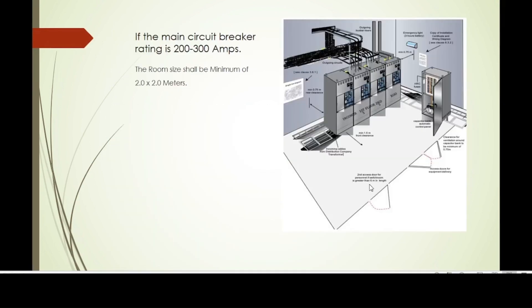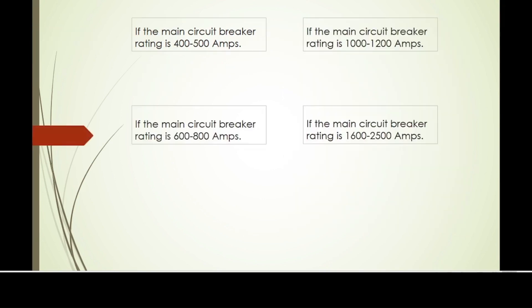As per ADDC electricity and wiring regulations 2020, appendix 8, there are certain minimum sizes for LV switch rooms based on their respective main circuit breaker amperes. For example, if the main circuit breaker rating is 200 to 300 amps, the room size shall be a minimum of 2 by 2 meters. Similarly, if the main circuit breaker rating is 400 to 500 amps, the LV switch room size shall be a minimum of 2.5 by 2 meters.